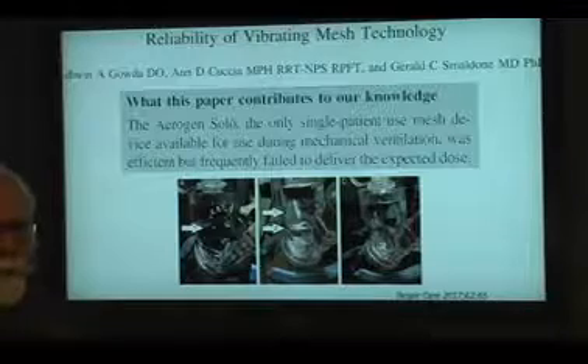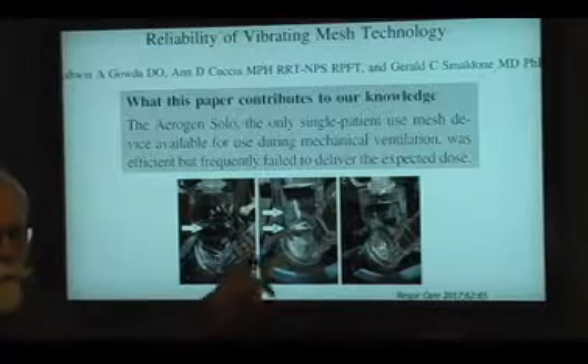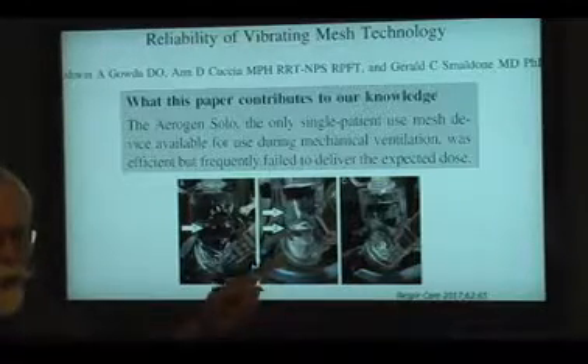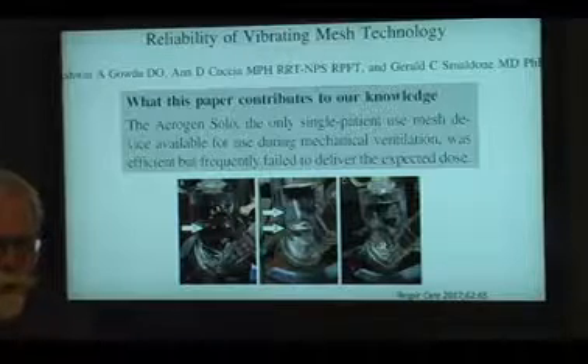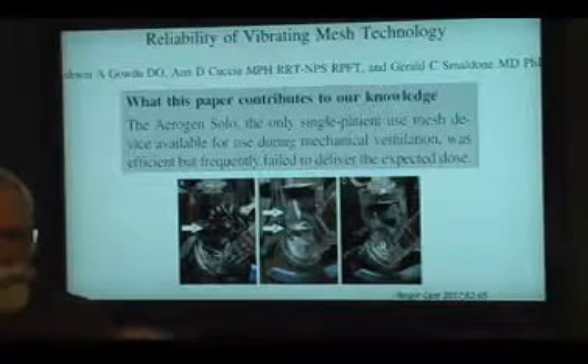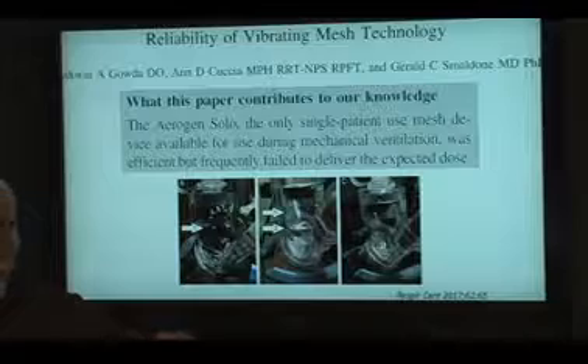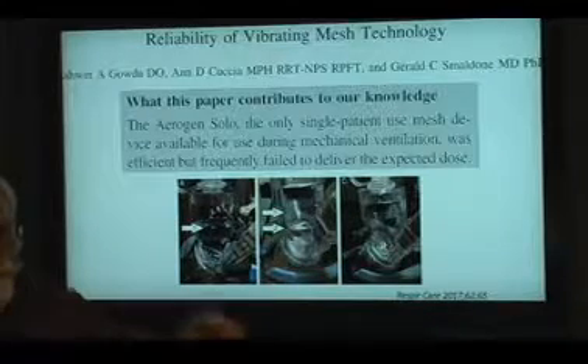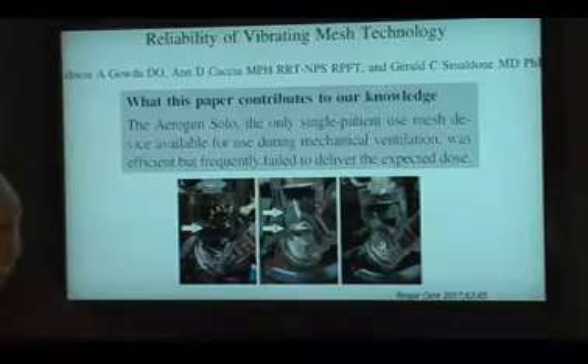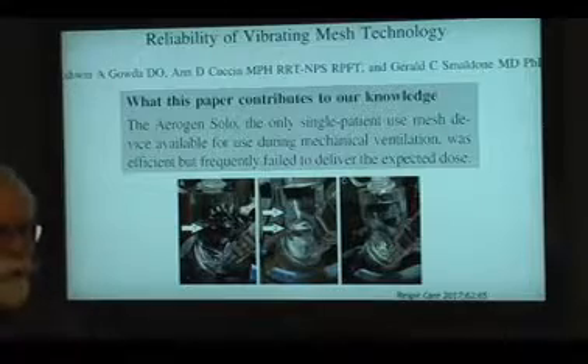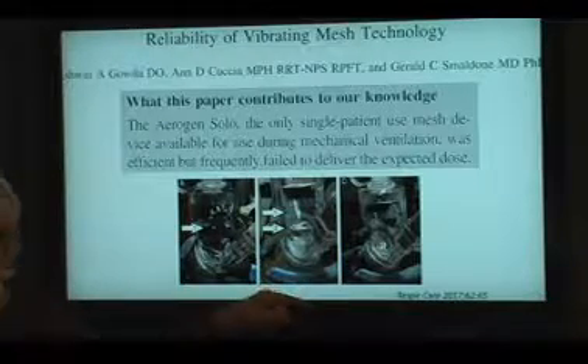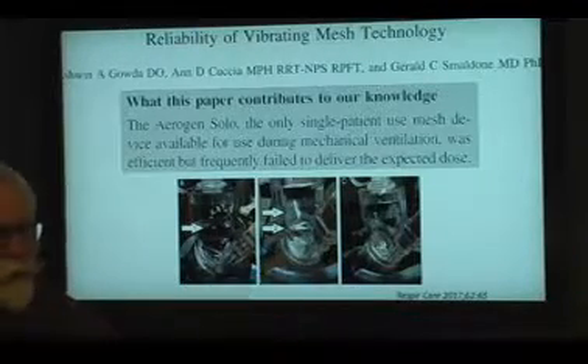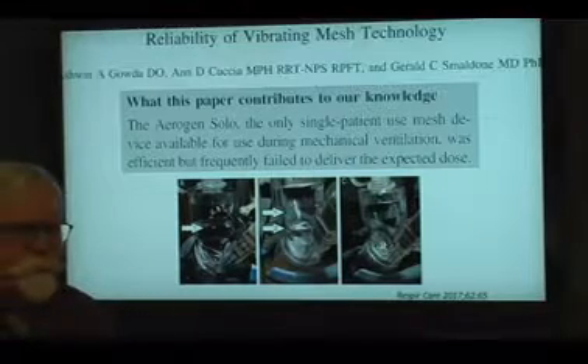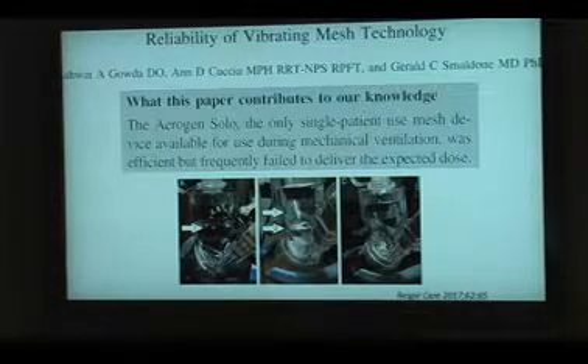Another issue with mesh nebulizers that's not commonly appreciated is that if you get moisture under the mesh, it won't work. That's why they get placed on the dry side of the humidifier. If you put it on the wet side and get humidity under the mesh, it fouls the system and stops working.